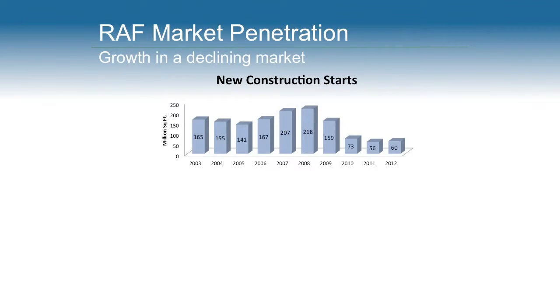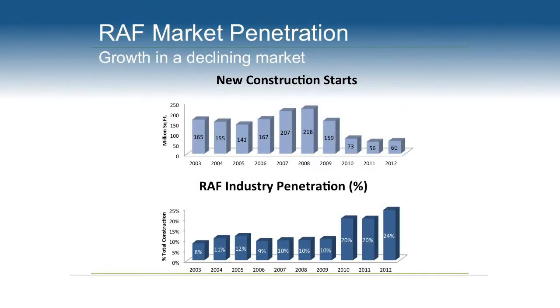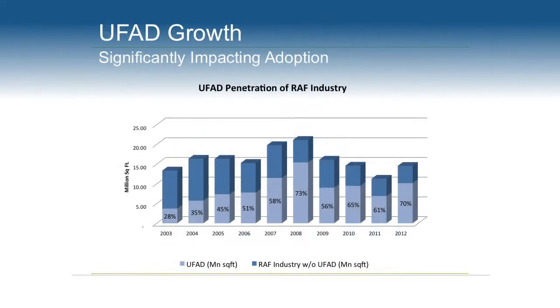So what I'd like to do is share some macro numbers of what's going on with the marketplace, how much of this is out there, in a declining construction start market, as you can see here back through the last decade. In terms of adoption of raised access floor, penetration of buildings, we're now in excess of 20% of buildings in the commercial, industrial, and institutional marketplace—24% of those buildings have a raised floor. And of that 24%, the big delta is that 70% now have underfloor air, versus when we got in the business in 1998, when about 3% of buildings had a floor, of which maybe 10% had the air, typically in the data center world. So this 70% is a big change in the marketplace and a lot of traction for underfloor air across the board.